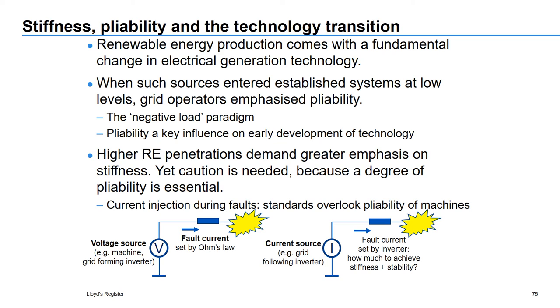But as renewable energy penetrations have increased so that they are now displacing synchronous generators to a much larger extent, of course, there is a need for a greater emphasis on stiffness. At the same time, though, we need to recall that a degree of pliability is essential, and so the performance standards we impose on those need to allow a degree of flexibility. When we look at fault current, for example, we need to recall that synchronous machine fault current is fixed by Ohm's law. It's not a fixed amount set by the machine, and it depends on the passive characteristics of the faulted network. When we try and replicate that in inverters, we need to ensure there's a degree of flexibility so that while a certain amount of fault current is being produced, contributing to the stiffness of the network, that is not so great that it actually destabilizes the network, as in fact it can do.